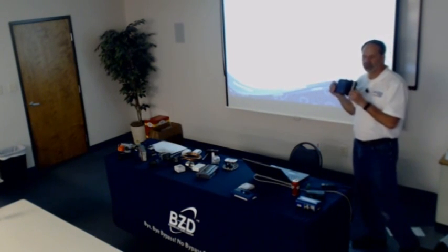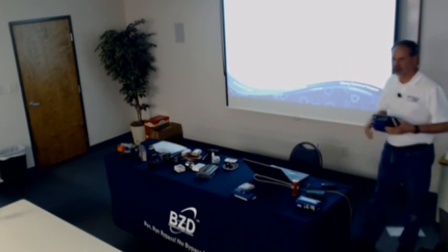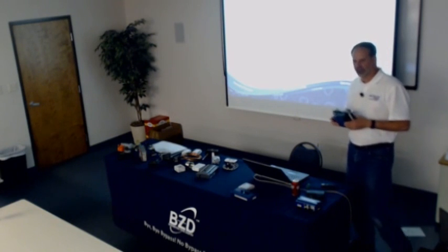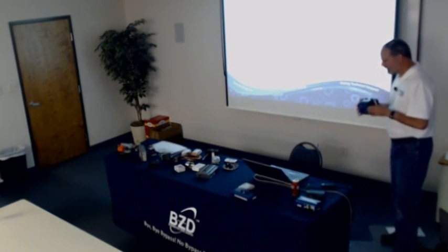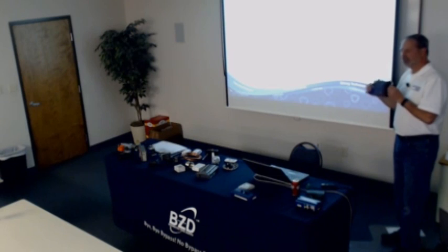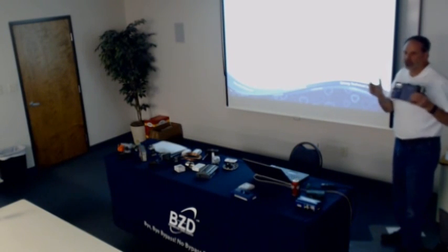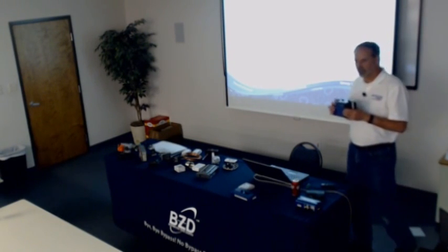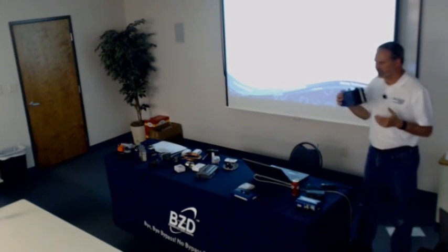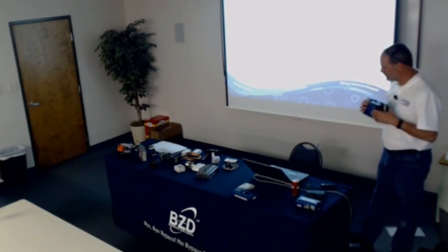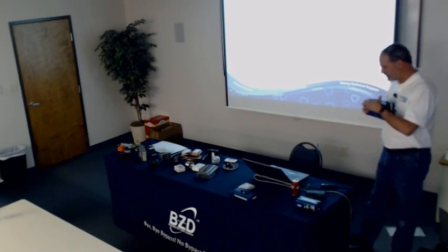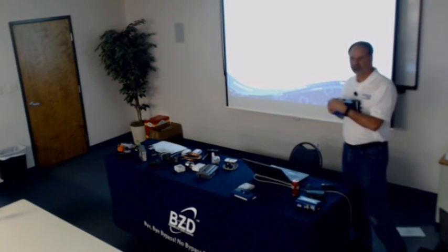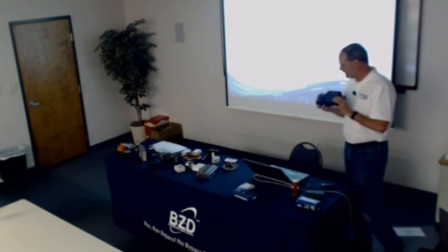It has an input that you can set up as a door switch, so if it's in a classroom and somebody goes and opens the window, it shuts off the air conditioning. Doesn't make sense, running the air conditioning if they've got the windows open. So it's a VAV box controller. That's all it does. That's all it'll ever do. It does a great job. But it has a set of ways to do what it does, and that's all it does. You can't change it into a rooftop controller. It just won't do it.